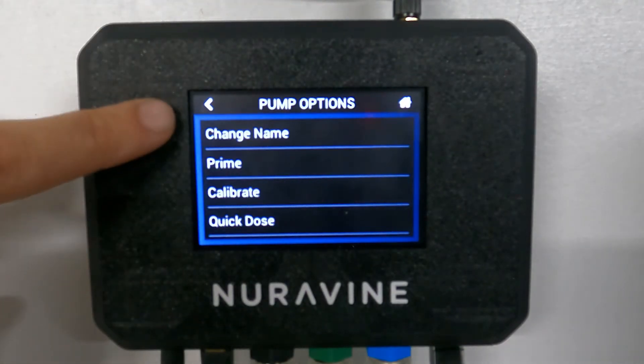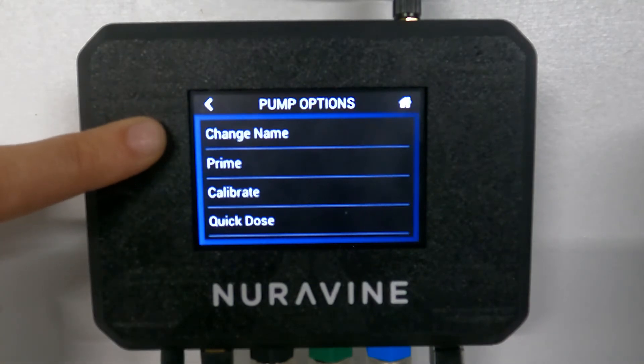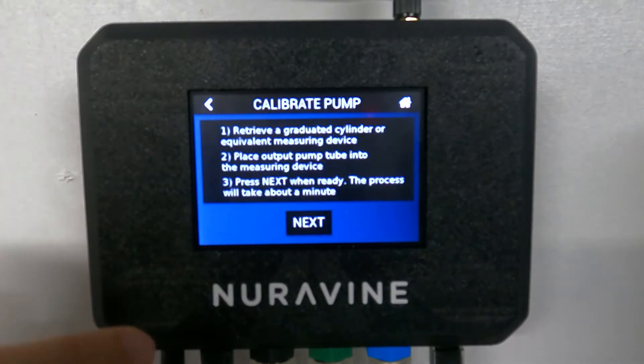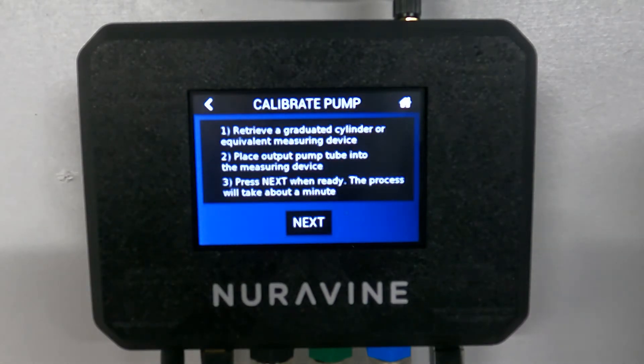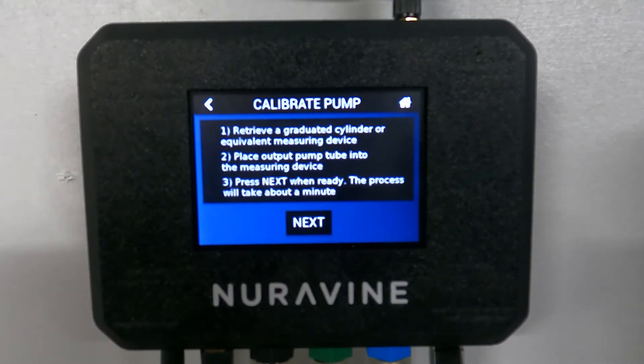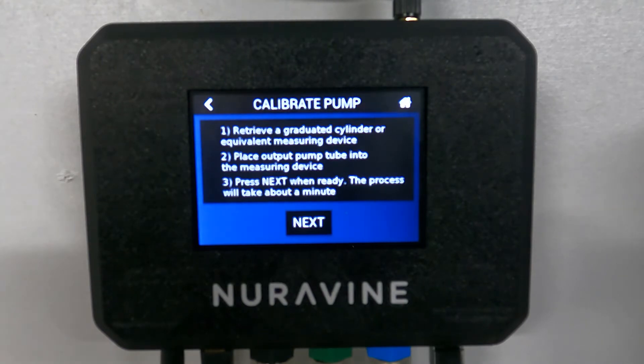Clicking on the pump, you're going to see a bunch of different options: the option to change the name of the pump, to prime the pump, and to calibrate the pump. For calibration, you're going to have a beaker or some measuring device. These pumps can pump up to about 200 milliliters per minute and the calibration runs for a minute, so you need a device that can read down to one or two milliliters but also hold over 200 milliliters — you'll need a large beaker.